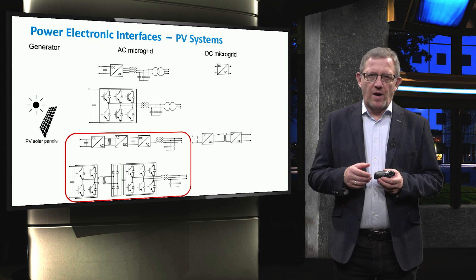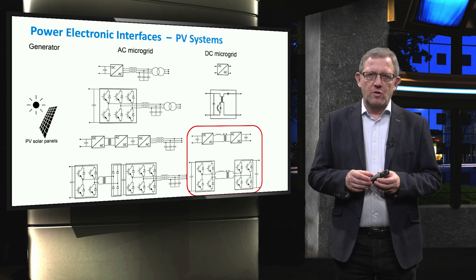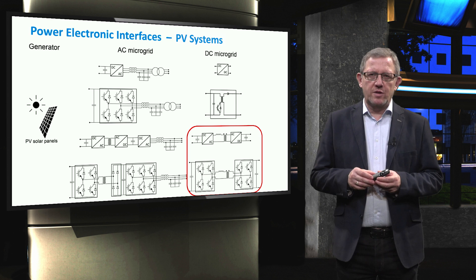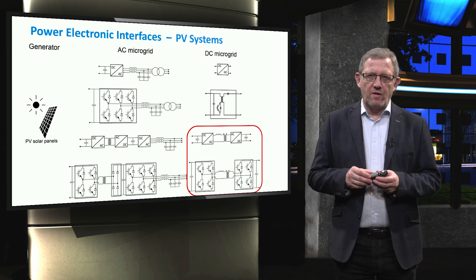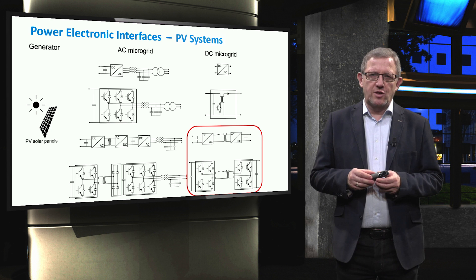To connect a photovoltaic unit to a DC microgrid, typically a boost DC-DC converter is used where the DC link voltage of the grid has a high value. To increase the performance and efficiency, a dual active bridge converter topology is often used.